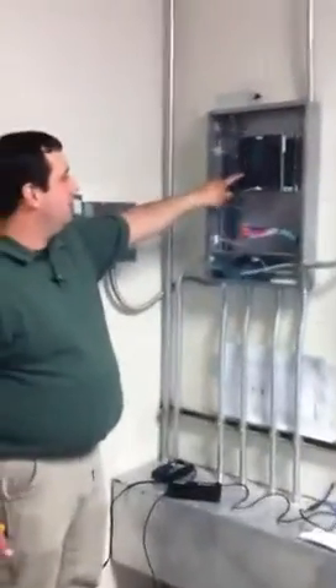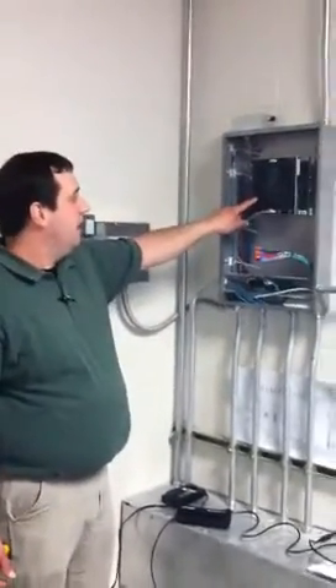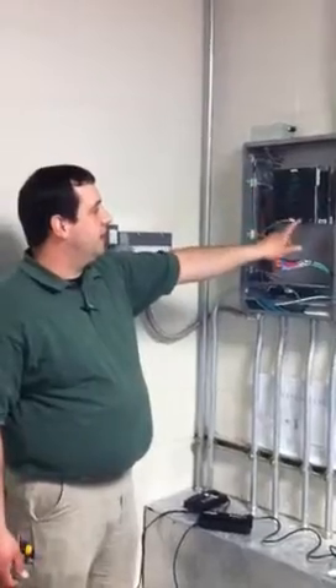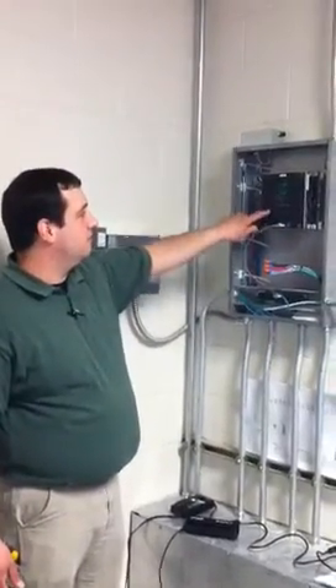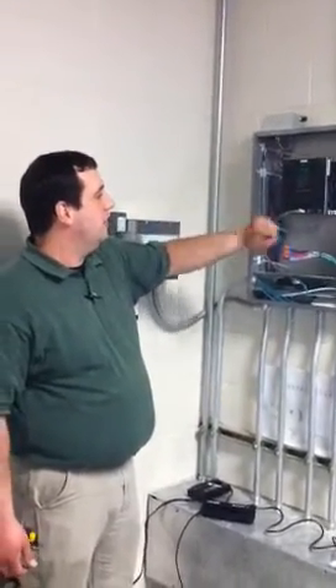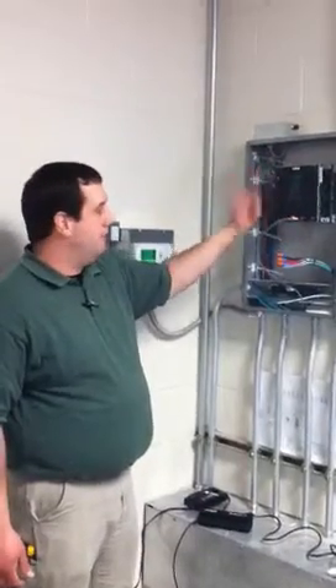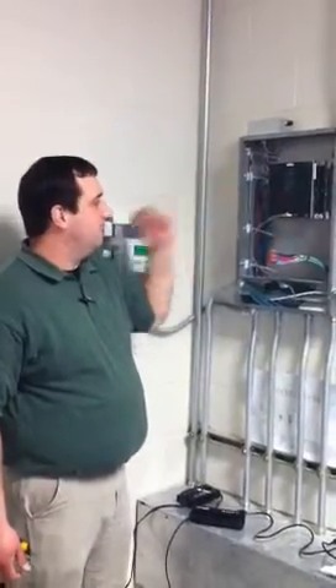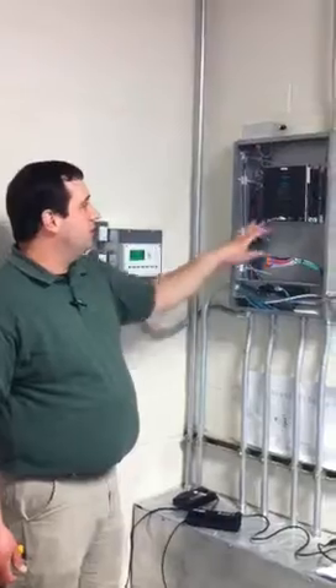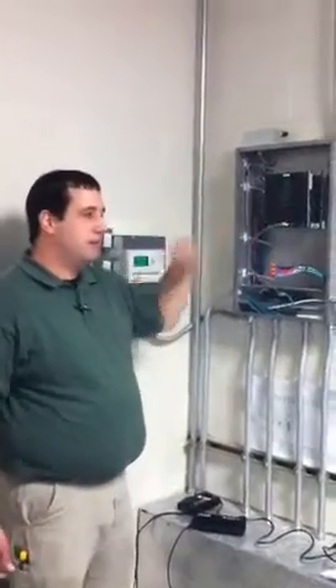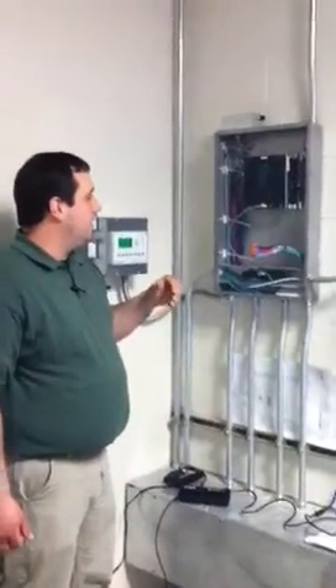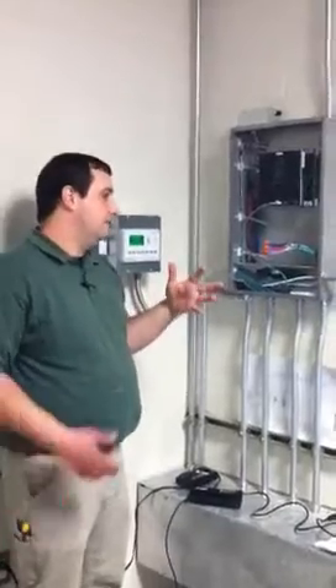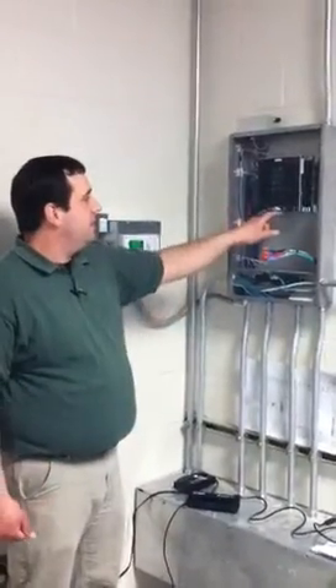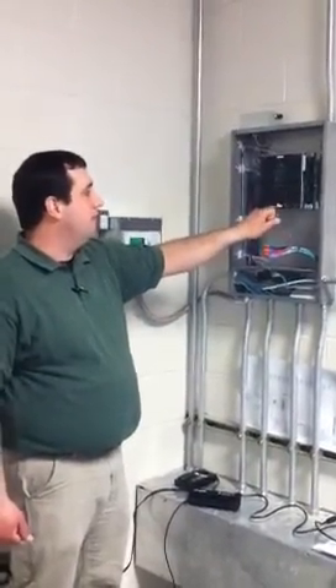Individual relays tell you if the output is on or off, and you can turn the individual relays on and off by hitting the on and off button next to it. It'll also update the status in the window as well. When the LED is on, obviously the load is on; LED is off, the load is off. You can turn the individual loads on and off from the buttons on the front, but when the scheduler triggers, say the scheduler triggers an off event, the scheduler will turn those off.